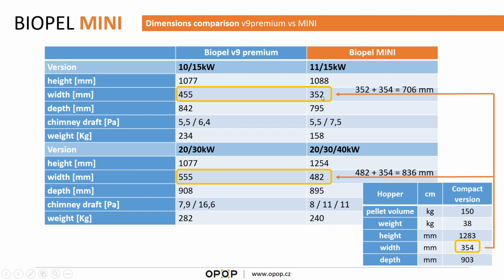352 millimeters. And if we go here, we see the hopper version for Biopel Mini with the size of 150 kilos of pellets, which has a width of 354 millimeters. So if you put this size together with the size of the boiler, you get these numbers. So the standard compact installation is only basically 700 millimeters wide, and with the bigger boiler it is again less than 1 meter, 836 millimeters wide. So the installation is quite small, and the same goes for depth or height of the boiler, but with the width it's really easy to see the difference.